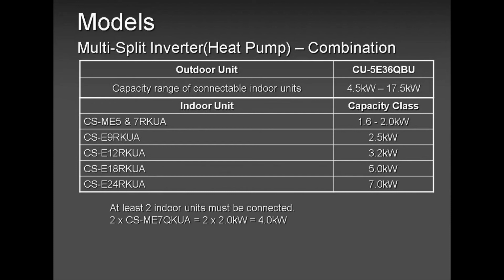Okay, guys? And QBU is the series and version for heat pump. And -5, guys, stands for -5 degrees Fahrenheit. So you can operate this unit all the way down to -5. It will not shut off on you. If you operate below -5, it will try to keep up as much as it can, and eventually it will slow down and shut off. But you will not get any error codes, okay, guys? If it operates way below -5, it will just stop producing heat.